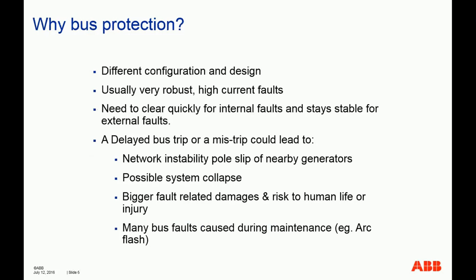So why bus protection? Bus faults usually are very robust, but they are also very rare. However, when it happens, chances are they are very severe. Seriously, things have gone wrong. Also, because of the different bus configurations available under deployment, different types of bus protection schemes are available to protect different types of bus configuration. In general, bus faults need to be cleared very quickly, especially internal faults, and you need to stay stable for external faults.